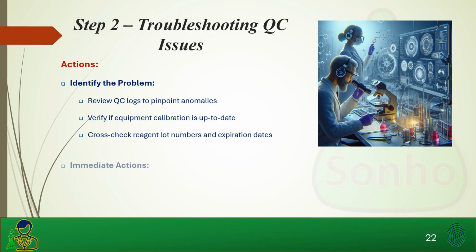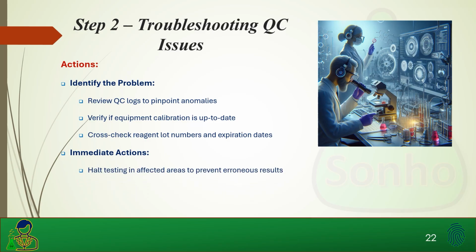So, immediate actions. Halt testing in affected areas to prevent erroneous results. Rerun QC samples to confirm the issue. And notify the lab director and supervisor of findings. Remember, oftentimes you cannot release reports without a passing QC.